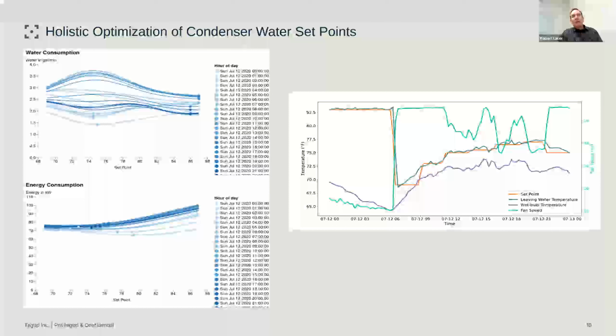On the right hand side, this is more rule-based - nearly a fixed approach type of signal where you raise and lower the set point based on the wet bulb temperature. But on the left, it's very much not so. That has a lot to do with factors like the load that the system learns about, and at what point we actually have to switch away from a simple rule-based strategy and go to something that truly optimizes the system under the given conditions.